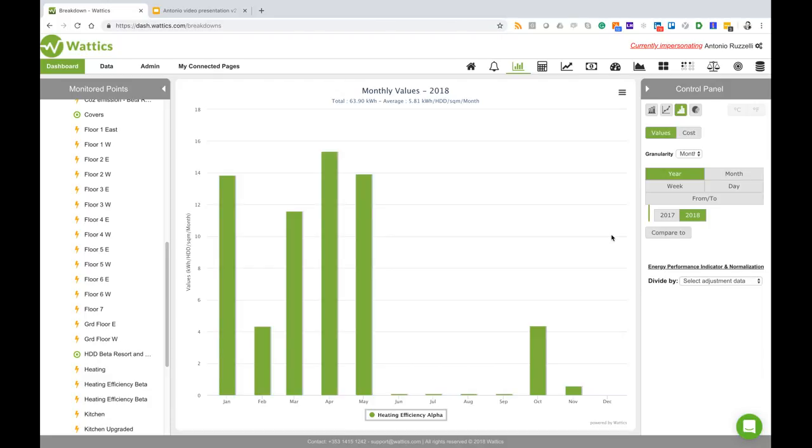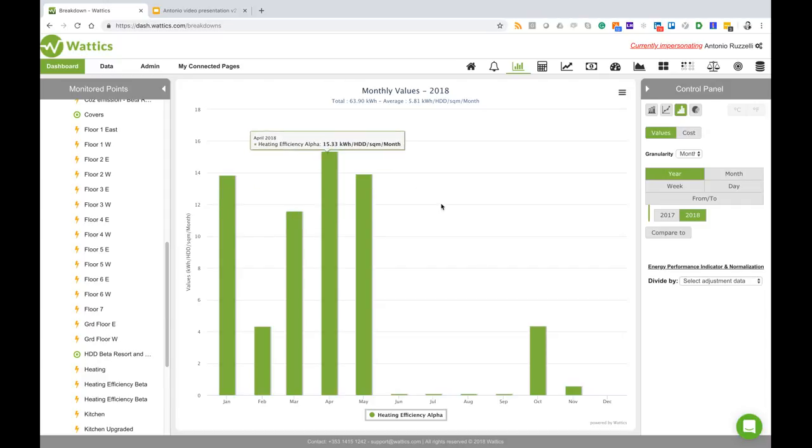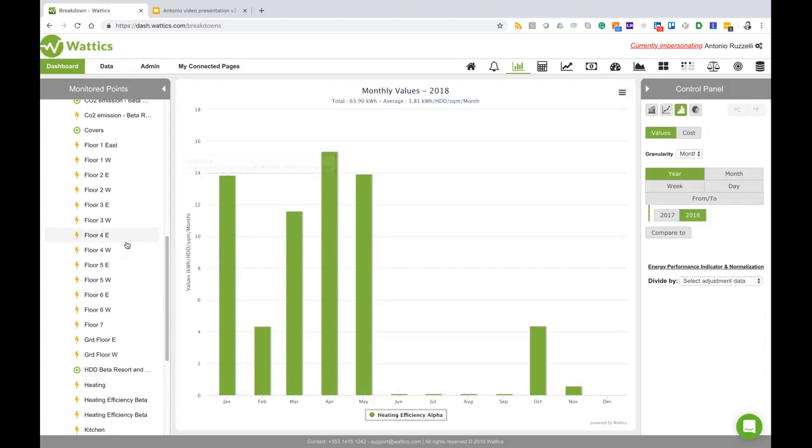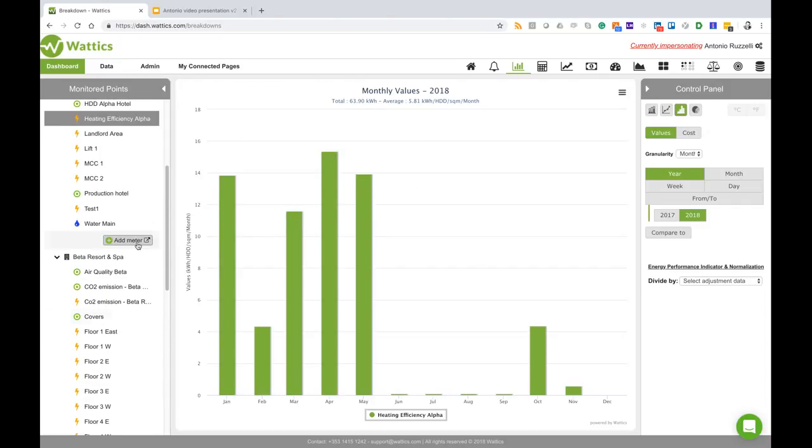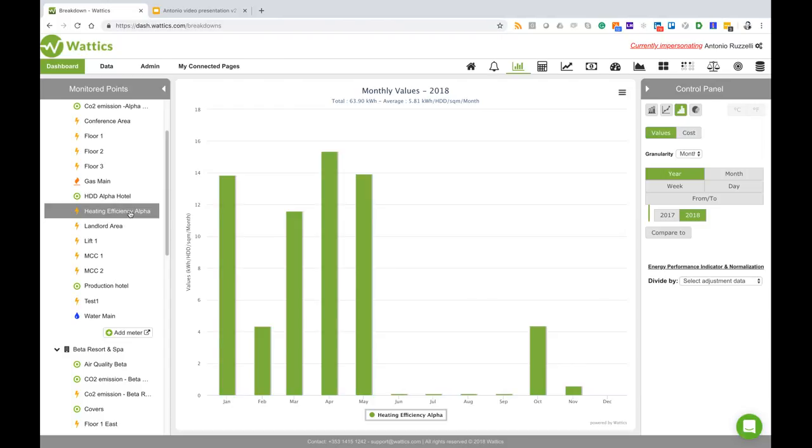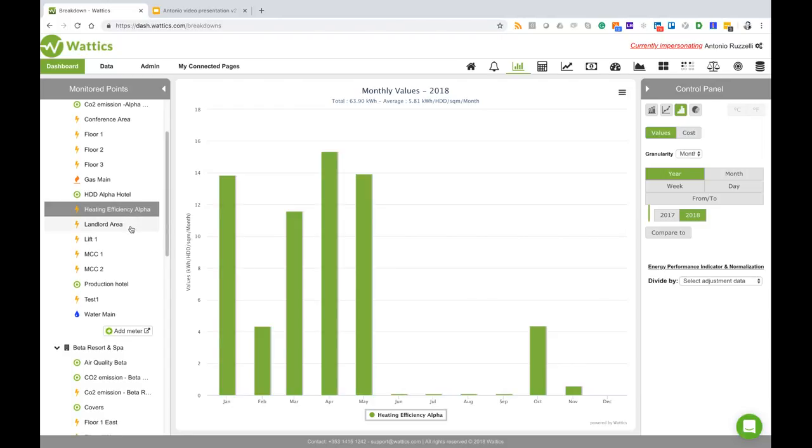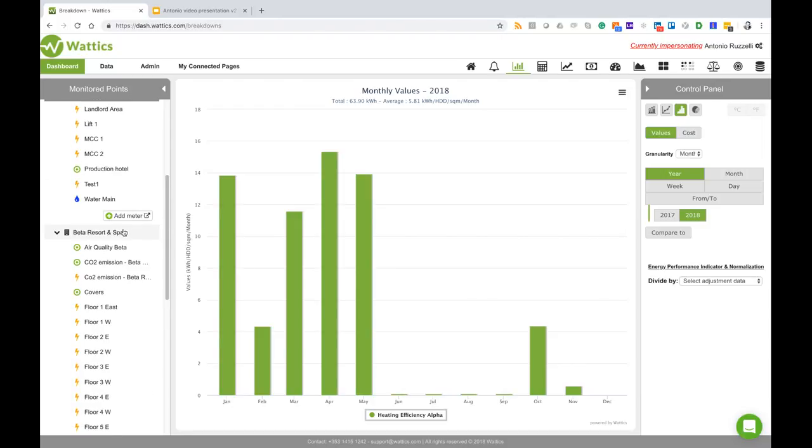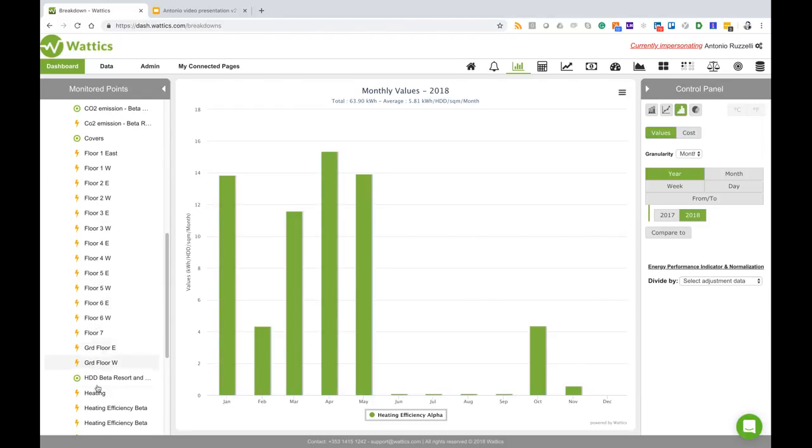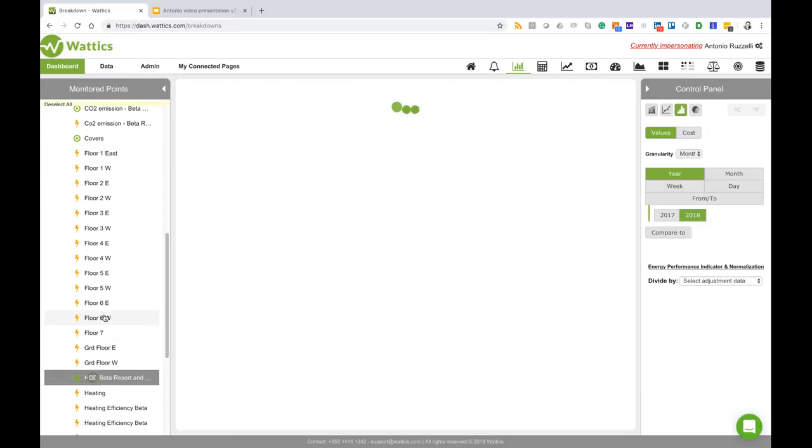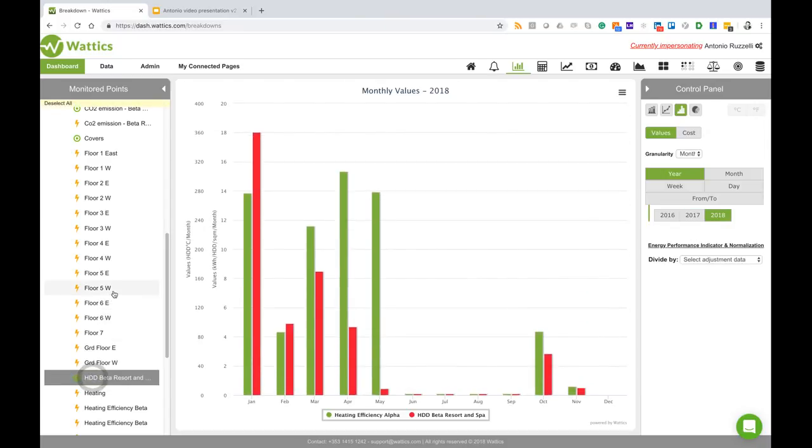My Alpha Hotel instead required 63 kilowatt hour efficiency in 2018, which is the kilowatt hour by the heating degree days by the square meter per month. This means that Alpha Hotel is way more efficient than Beta, so if I have some budget to spend to improve insulation of these two hotels, I would certainly spend the money on Beta and not on Alpha.